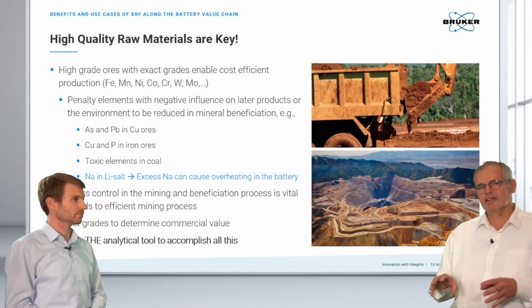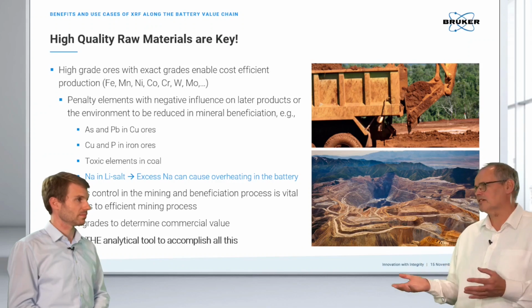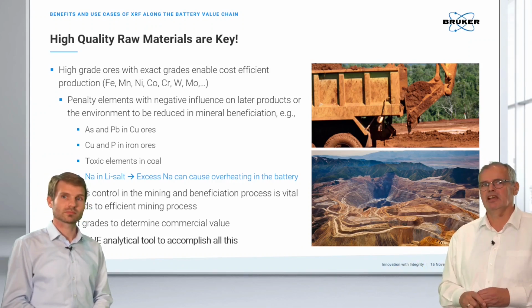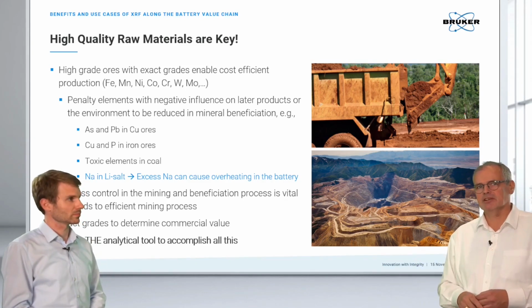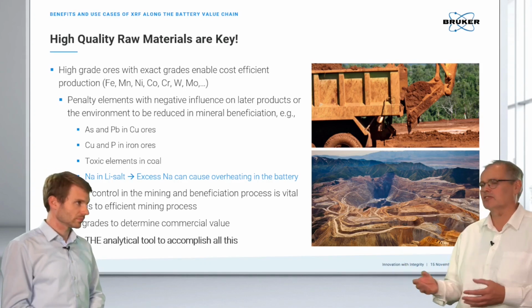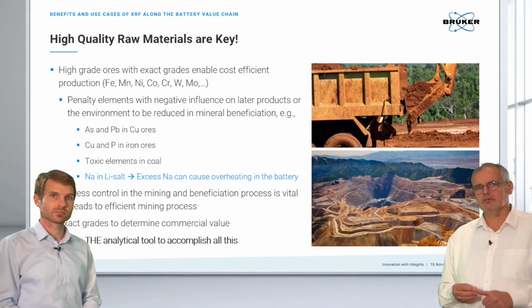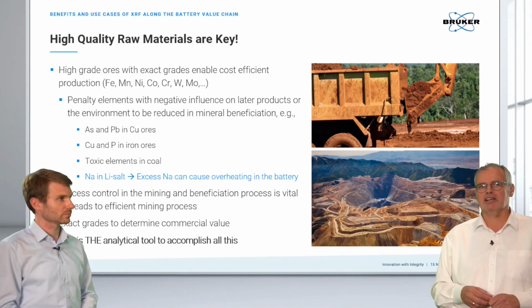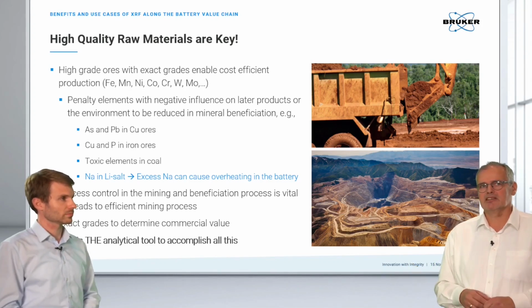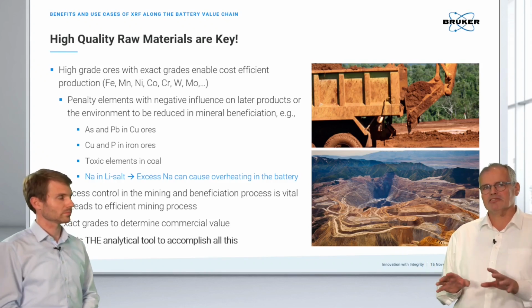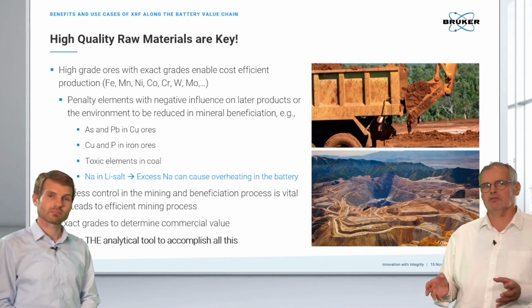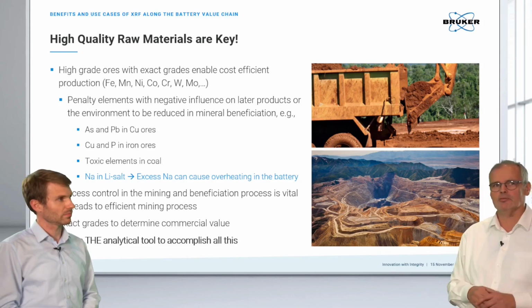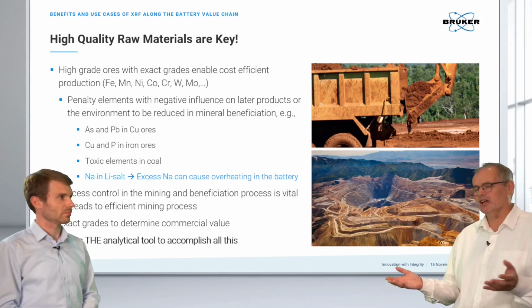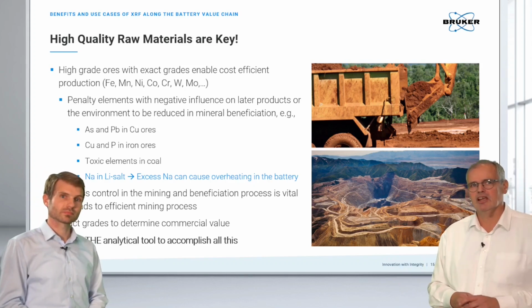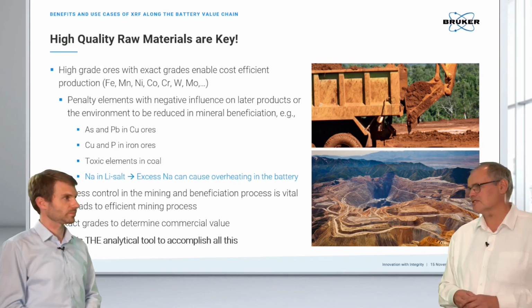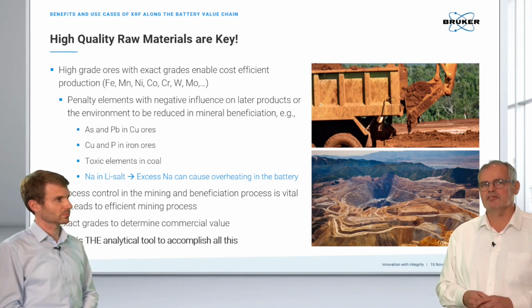Yeah, we learned that the technology is quite robust on the one hand, but also handles solid samples directly with high precision and accuracy. When we look into mining operations, that's a big investment, and it's a valuable material flow. So on the one hand, we need to determine very accurately the ore grades or the grades of the concentrate, the value-determining element, is it copper, nickel or cobalt? But there are also some impurities involved in the value chain, the penalty elements. Copper ore can contain arsenic and lead, which will later lead to negative effects in the product. In iron ore, copper, silicon or phosphorus will also determine the value of the iron ore.